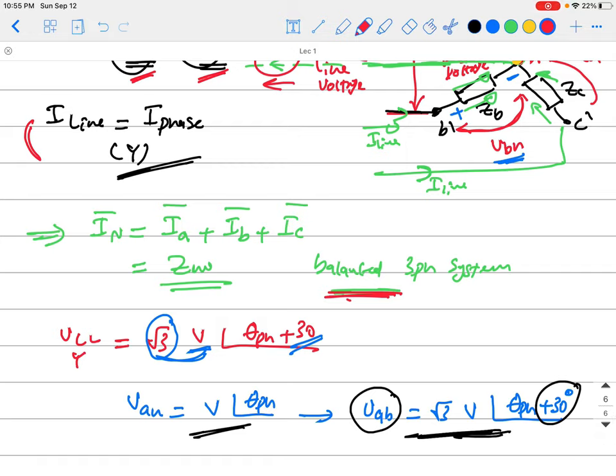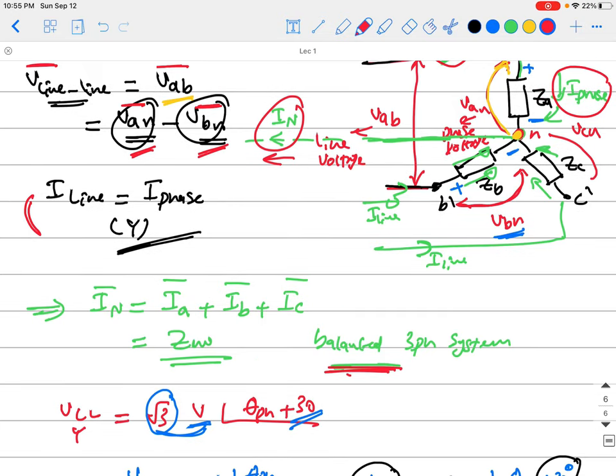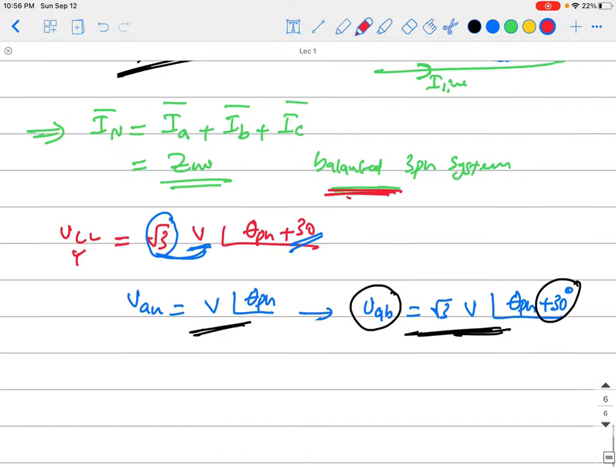For a balanced three-phase system, the sum of the three phase currents — which gives the neutral current — equals zero. That means no current flows through the neutral line. If any imbalance exists, meaning magnitudes are not exactly equal or phase differences are not exactly 120°, some current will flow through the neutral line. You can check if your system is balanced by measuring the neutral line current: if it is zero the system is 100% balanced.